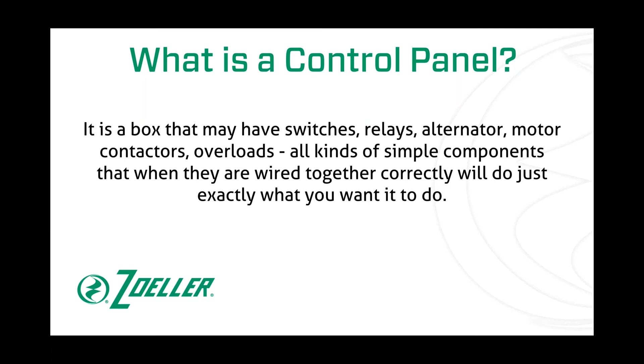So why would you need a control panel? It's a good question. There's a lot of reasons. It might be as simple as wanting to put an alarm and control functions together in one simple package. It might be that you have a big pump, say large horsepower, and you need a control panel to operate it. It might be that manual operation is desired, so you want to use a control panel. Perhaps you're going to be monitoring a big three-phase pump. That would be a reason you might need a control panel. Maybe you want an alternating duplex application. That would be a reason.